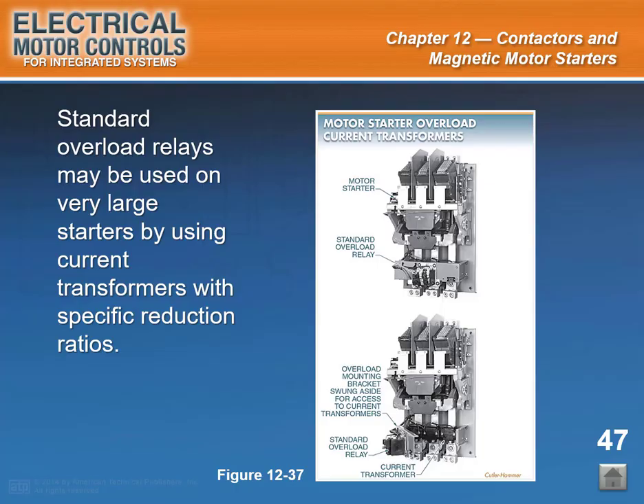A current transformer does not change the amount of current flowing to a motor but reduces the current to a lower value for the overload relay. For example, if 50 amps were flowing to a motor, only 5 amps would flow to the overload relay through using the current transformer. Standard current transformers are normally rated in primary and secondary rated current such as 50/5 or 100/5. End of slide 47.